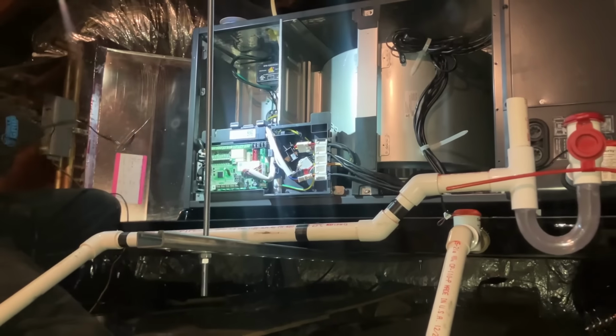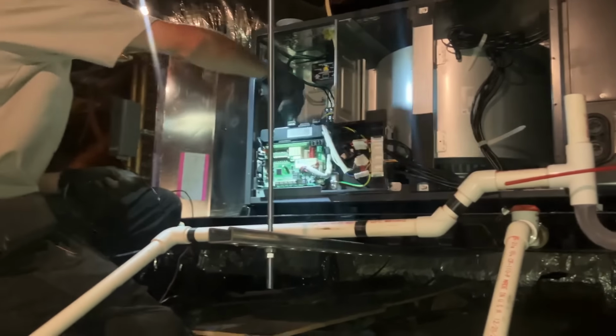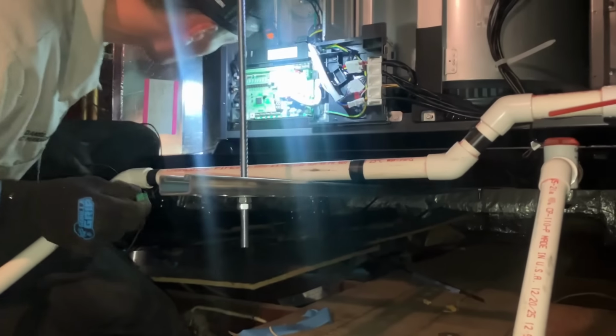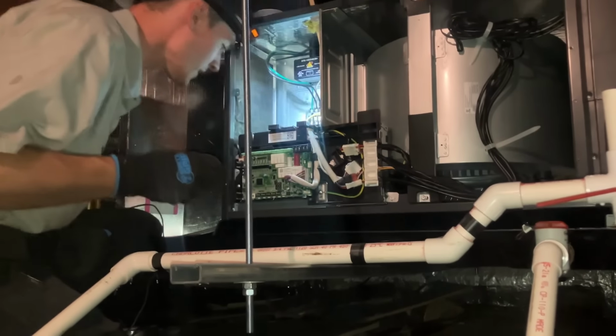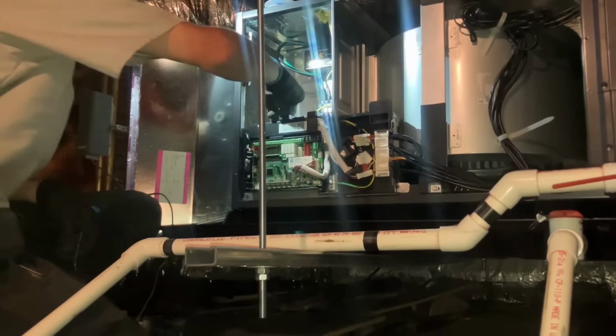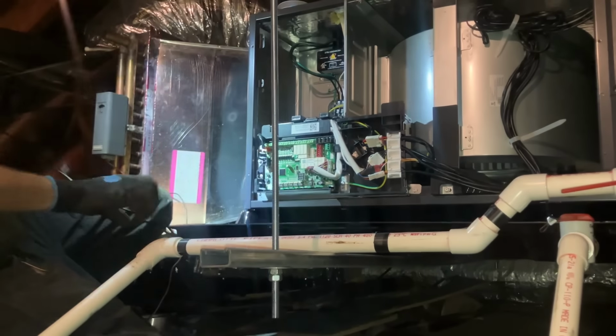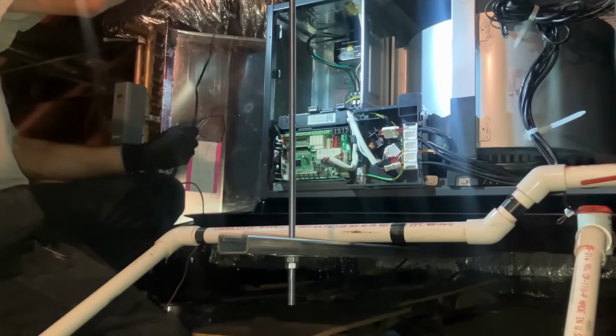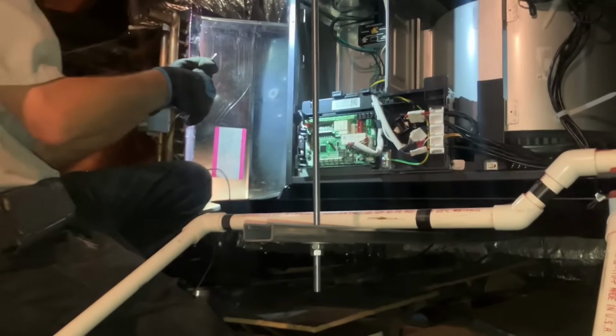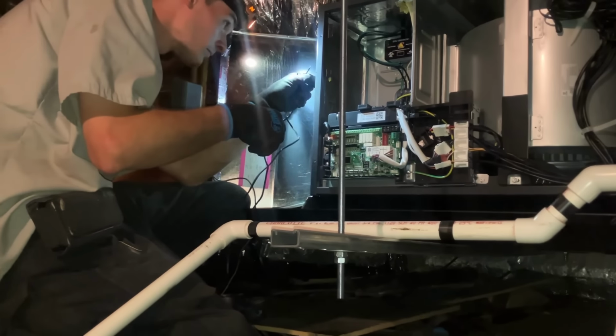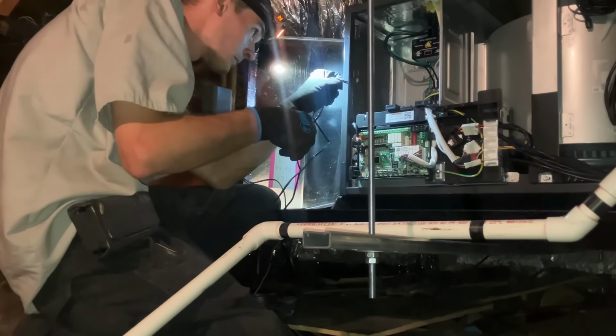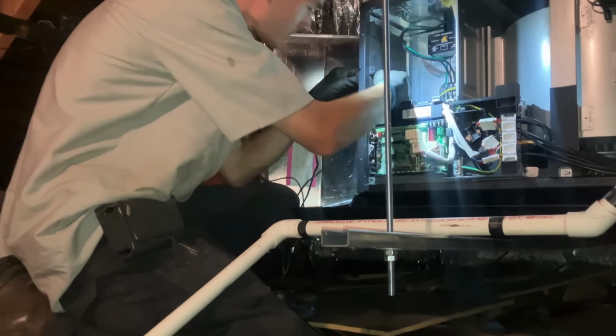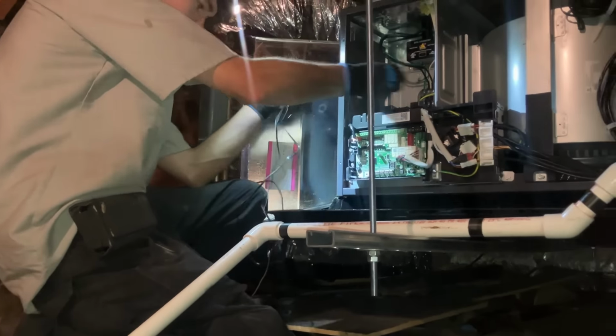So right now you're wiring the float switch to the terminals. What terminals, CN23? Yeah, CN23, perfect. So when you remove the jumper and wire CN23 in a communicating mode, the thermostat will let you know that the float switch is activated and you've got a clogged drain.